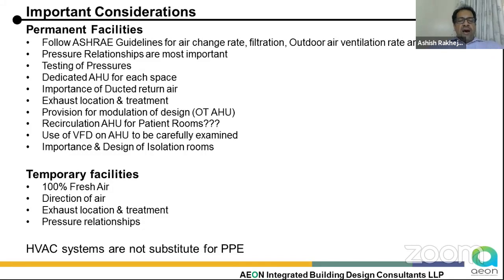I've been a big promoter of operation theaters with variable fresh air. That means that we should be able to take it from a minimum of 4 air changes per hour to a maximum of 20 air changes per hour. And I've always advocated that based on the procedure, one can change the fresh air rate which is being added in the room. And again, this crisis has shown such modular designs are the need of the day because we don't know what is going to strike us next, and medical facilities need to be ready for these unexpected conditions also.